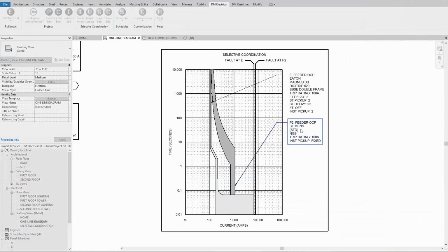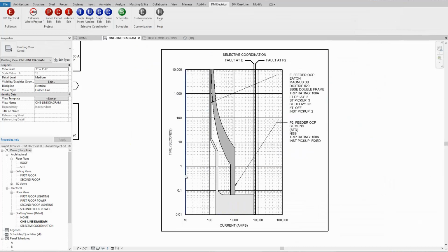It's actually not even showing up a little bit because of all the other settings. So there we go, we adjusted the short time pickup, and that pulled the curve up. These curves are also used for the trip time for arc flash calculations.